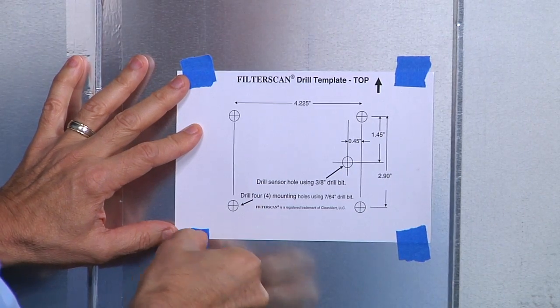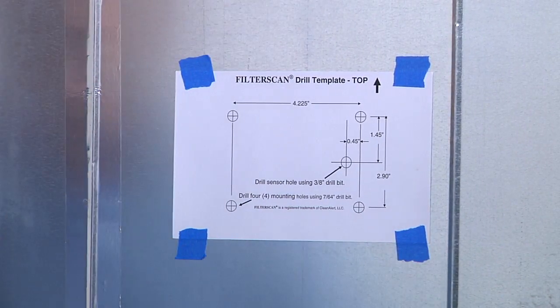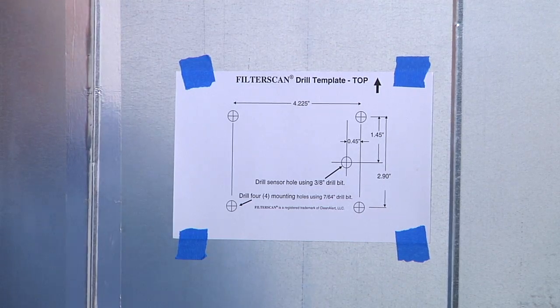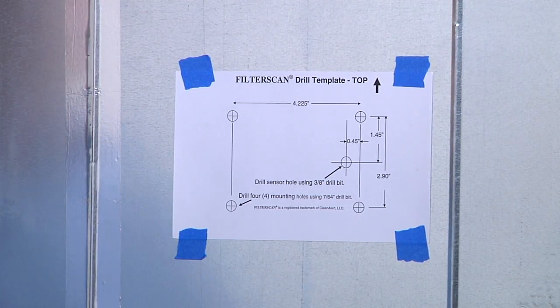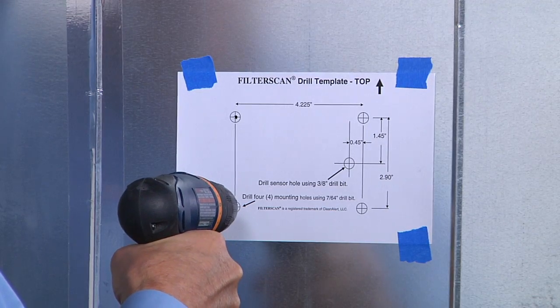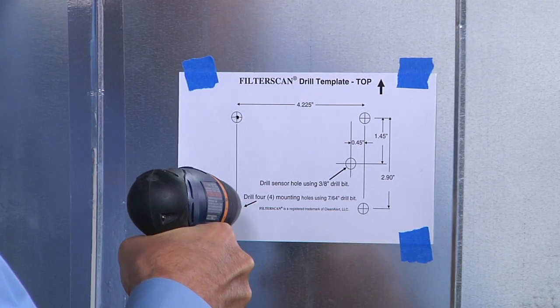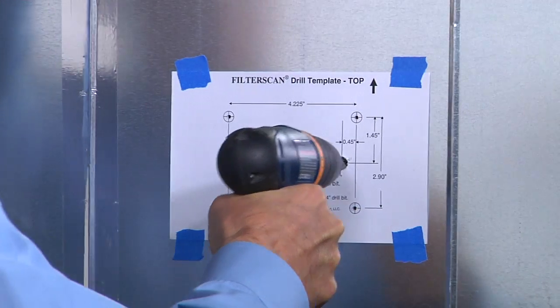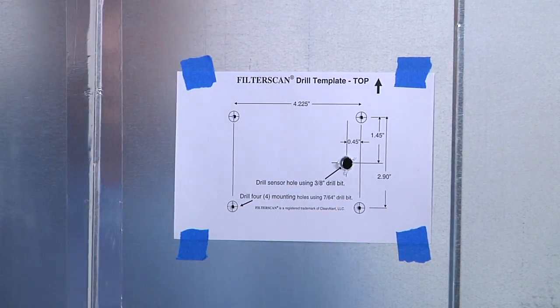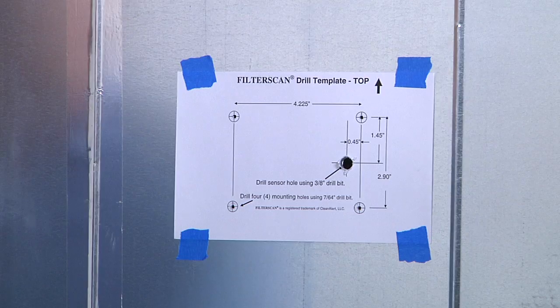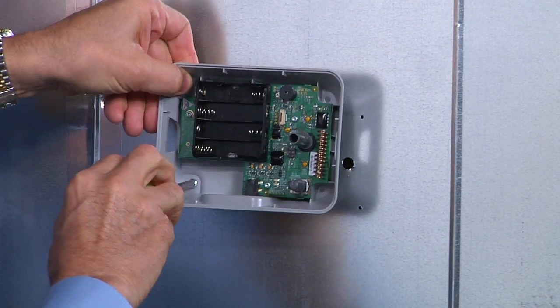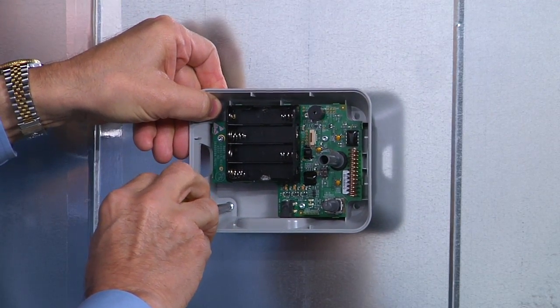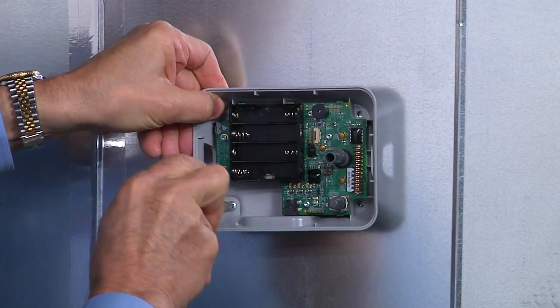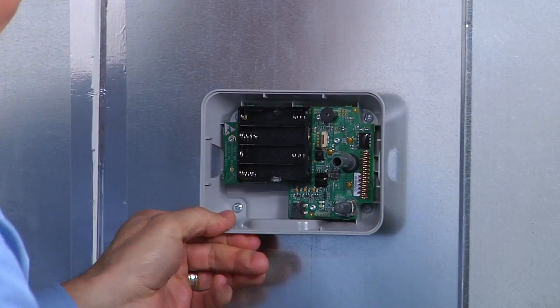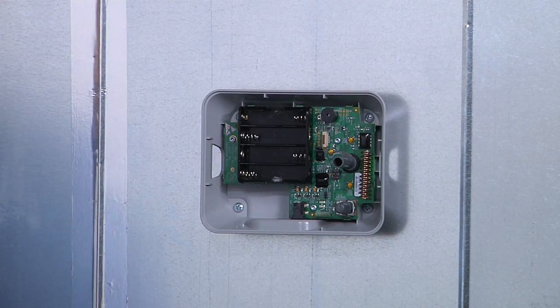Place the monitor template at the selected location such that top is facing upward. The monitor front panel must be clearly visible after installation. Drill 4 7/64" holes and 1 3/8" hole for mounting screws and for the sensor. Alternatively, the 4 mounting screws are self-drilling with no need for pre-drilling the mounting holes. Attach the Filterscan monitor by aligning its sensor tube with the larger hole and securing the housing using the mounting screws supplied. The sensor tube does not extend into the duct.